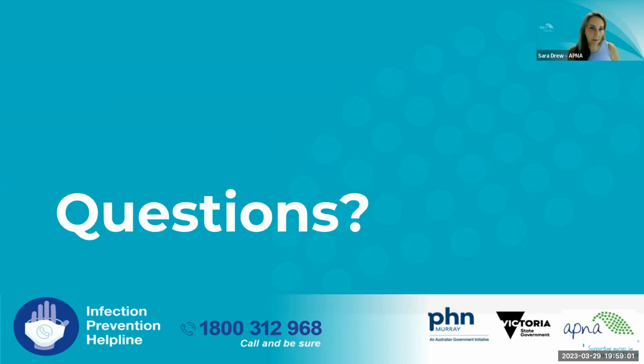The next one is from Carolyn. Carolyn's asking, hinged instruments, do they need to be fully open or partially open, unclamped when packing? They should be partially opened, but you really don't want them fully open, because sometimes these items are sharp as well, and that could actually cause a hazard. But as long as they're open to the point where they're hinged or ratcheted, the steam will be able to penetrate and then be drained off. Gone is the day of us having them all the way open and slid into the package, which of course can then pierce the packaging, etc.